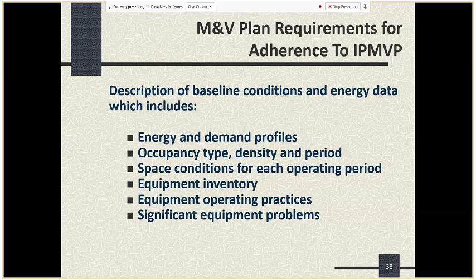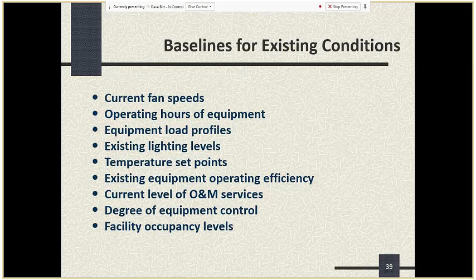Here's more variables. In your baseline, when you're looking at a specific system, current fan speed, operating hours, light levels, temperature set points, current level of O&M, degree of equipment control, all of these are variables that have to be thought of, and we tend to think, oh, I can just look at one number on my utility bill. No, you got to look at all these things. That's a lot of stuff to bear in mind, but you can't accurately define a baseline with just utility information. You've got to know all these other factors that are part of the baseline condition.